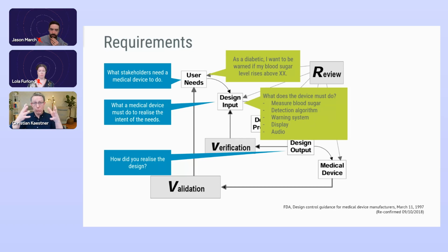However, you as a developer, you need to consider, what must the device do? Probably you're going in the direction of, you need to have some kind of measurement. There needs to be an algorithm detecting the levels. You probably need a warning system, and with that comes display and audio. So the design input will then refine the user need into more tangible requirements.